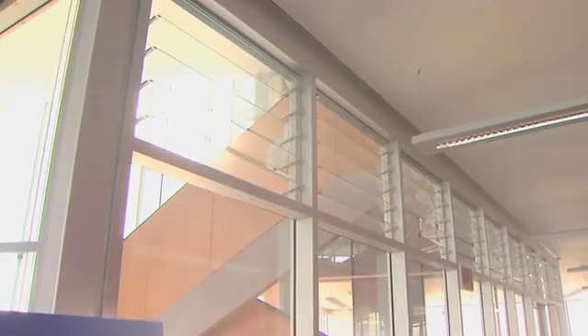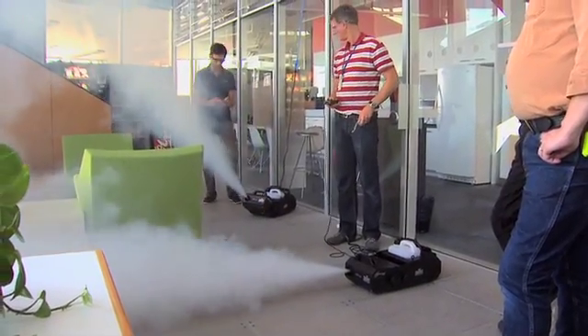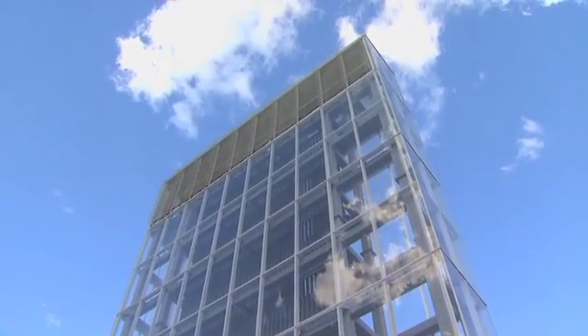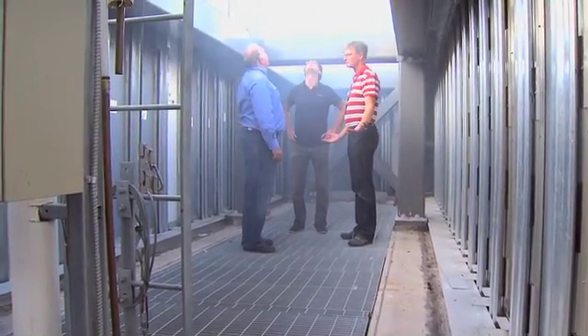Compared to a typical office space, especially in North America, we improve the air quality significantly — not only because of the displacement ventilation, where you provide the fresh air to the spots where you really breathe, but also because you do not recirculate air in that space. You get pure fresh air from the outside into the building, and it's exhausted to the outside.